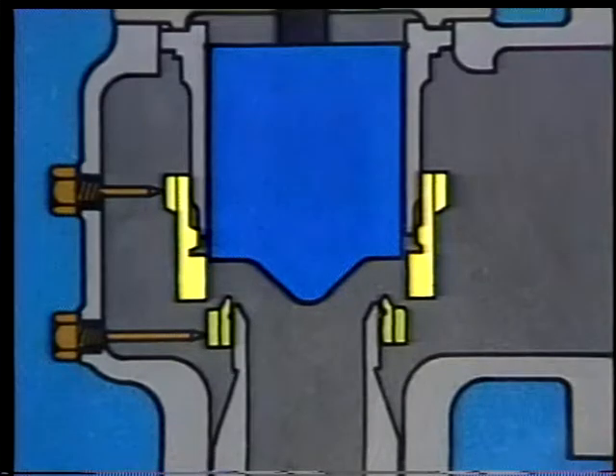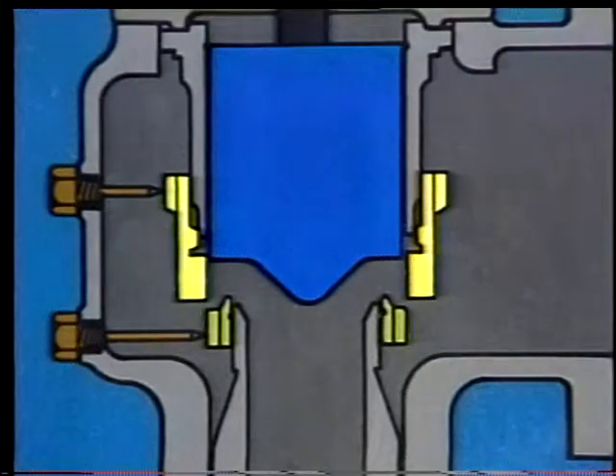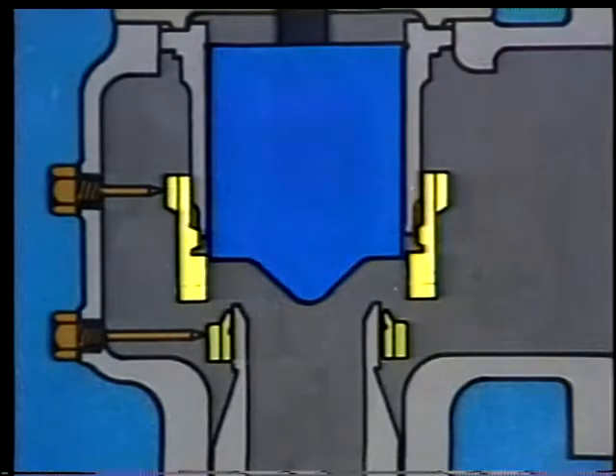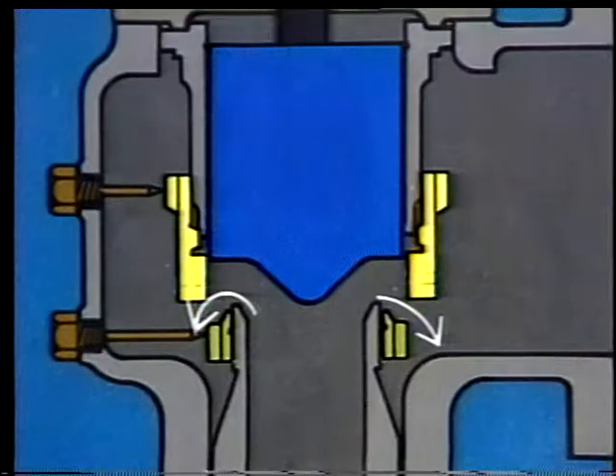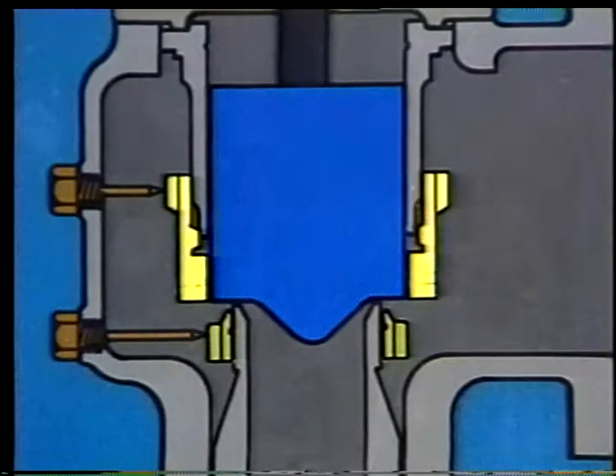If the lower ring is set too high, the space between the ring and the disc becomes too narrow. Because steam cannot escape as quickly through this narrow space, the blowdown of the valve is increased. Setting the lower ring too low allows the steam to escape without hitting the disc. The valve could simmer too long before popping, or it may not pop open at all. In addition, if the lower ring is set too low, no cushion of steam is formed to soften contact when the valve snaps shut. You can see then that proper positioning of the adjusting rings is extremely important.